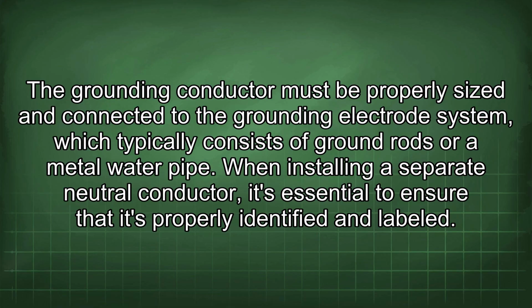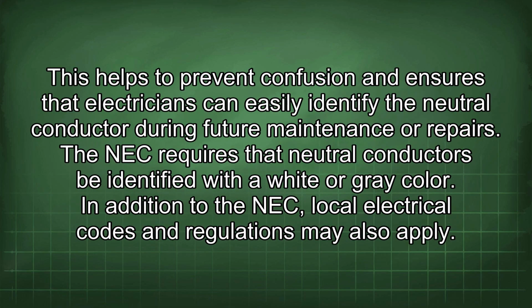When installing a separate neutral conductor, it's essential to ensure that it's properly identified and labeled. This helps to prevent confusion and ensures that electricians can easily identify the neutral conductor during future maintenance or repairs. The NEC requires that neutral conductors be identified with a white or gray color. In addition to the NEC, local electrical codes and regulations may also apply.